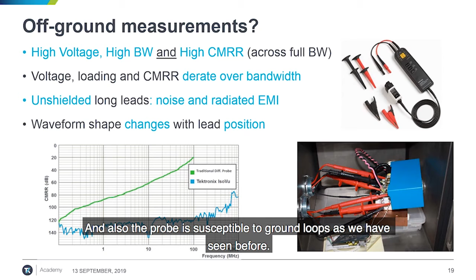The long leads of this probe make it susceptible to noise and radiated emission as well. This means that the waveform shape changes based on the lead length and the position of the probe, and so on. The probe is also susceptible to ground loops, as we have seen before.